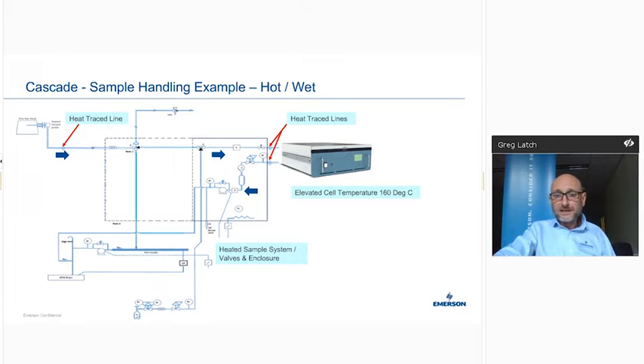And then you can see that second arrow, we're now running through a particulate filter, just for any remaining loading, if there is any particulates or loading elements. And then from there, we're going straight into what we call a quantum cascade laser analyzer. And this particular unit has an elevated cell temperature also at 160 degrees Celsius. So the subtle difference is we're having a heated trace sample from point of takeoff all the way through the sample handling system without any liquid or moisture extraction, running everything at an elevated temperature above dew point, running it through the cell.